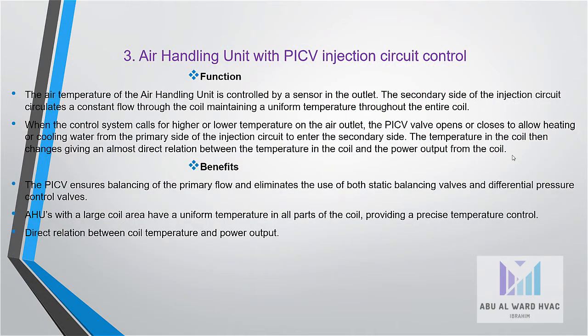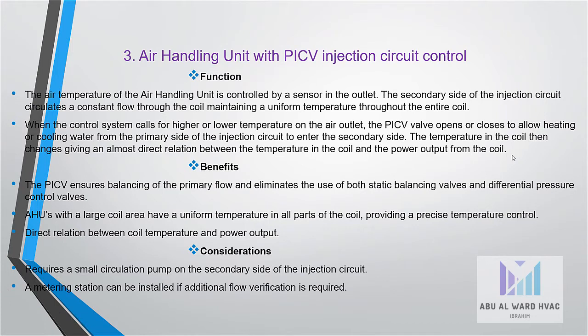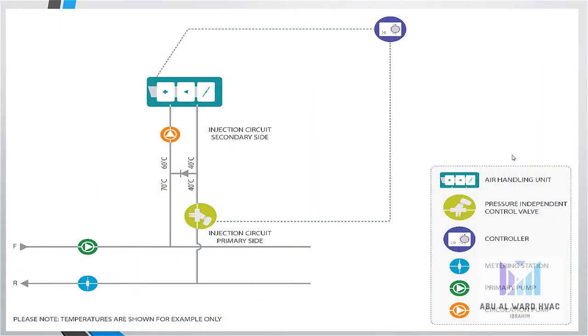The benefits: the PICV ensures balancing of the primary flow and eliminates the use of both static balancing valves and differential pressure control valves. AHU with a large coil area have a uniform temperature in all parts of the coil, providing a precise temperature control. Direct relation between coil temperature and power output. Considerations: requires a small circulation pump on the secondary side of the injection circuit. A metering station can be installed if additional flow verification is required. And here is the schematic diagram for this type of air handling unit.